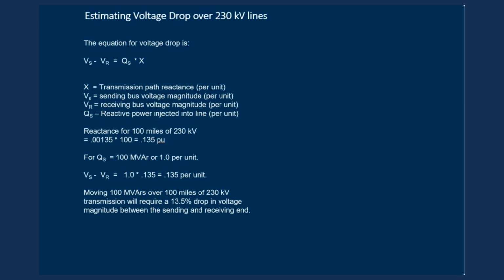So we have a generic equation that can be really useful, and that is when we look at the sending voltage minus the receiving voltage is the reactive power flow times the path reactance. So if we say the reactance for 100 miles of 230 kV is 0.00135 times 100, that's 0.135 per unit. If we say we're looking at 100 megavars, or 1 per unit of reactive power flow, then our sending minus receiving voltage is simply 1 times 0.135.